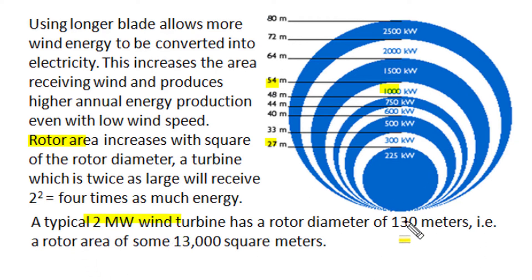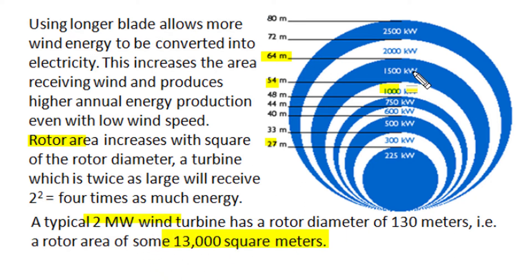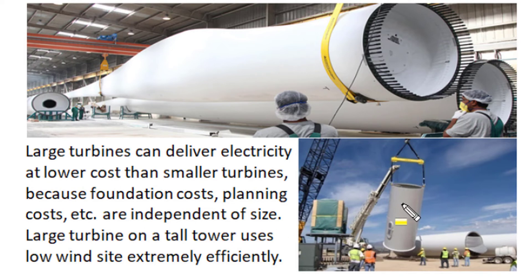Typically, a utility high-power 2-megawatt wind turbine has a rotor diameter of 130 meters with rotor blade dimension of 64 meters, making a rotor sweep area of around 13,000 square meters. That can ultimately produce 2 megawatts of electrical output at rated wind velocities of 10 to 15 meters per second. It has now been proved that large turbines can deliver electricity output at lower cost than smaller turbines.